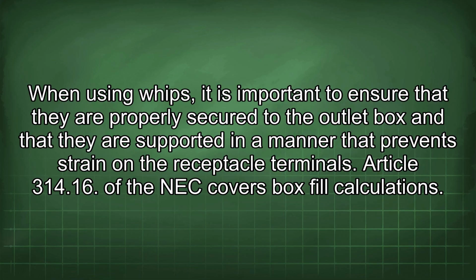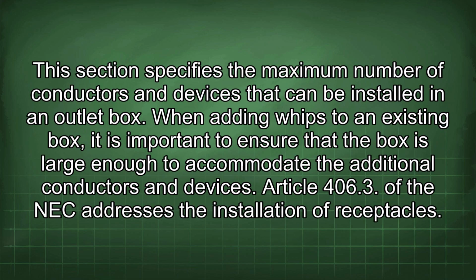Article 314.16 of the NEC covers box fill calculations. This section specifies the maximum number of conductors and devices that can be installed in an outlet box. When adding whips to an existing box, it is important to ensure that the box is large enough to accommodate the additional conductors and devices.